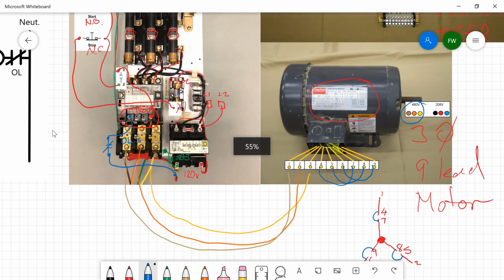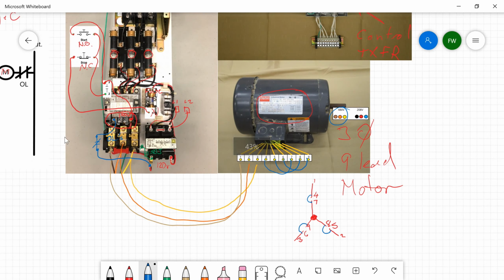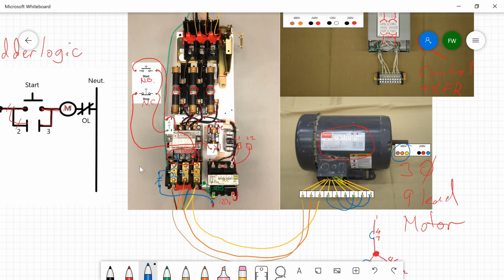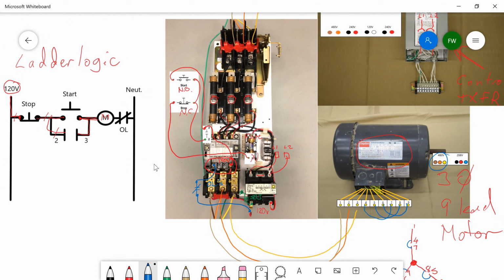All right, so that completes a simple start-stop. And if you look at your ladder logic, we have just taken our neutral and hooked it up to our overload. And from our overload, we've connected it to the motor starter contactor. And that will complete the start-stop of a combination motor starter.